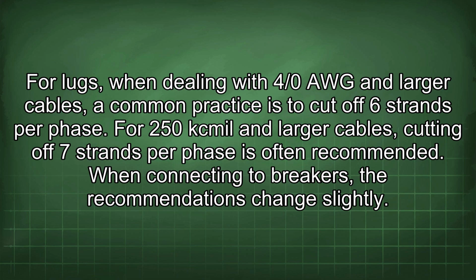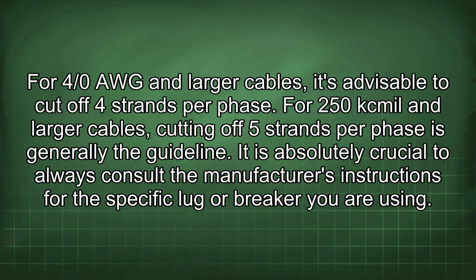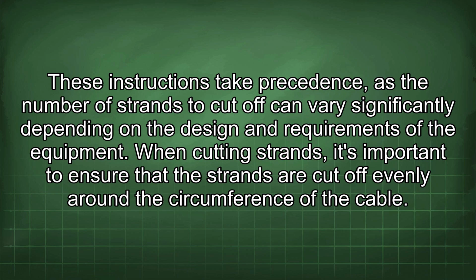When connecting to breakers, the recommendations change slightly. For 4/0 AWG and larger cables, it's advisable to cut off 4 strands per phase. For 250 kcmil and larger cables, cutting off 5 strands per phase is generally the guideline. It is absolutely crucial to always consult the manufacturer's instructions for the specific lug or breaker you are using.